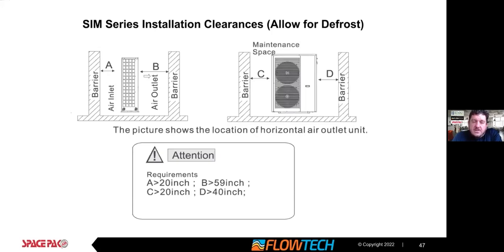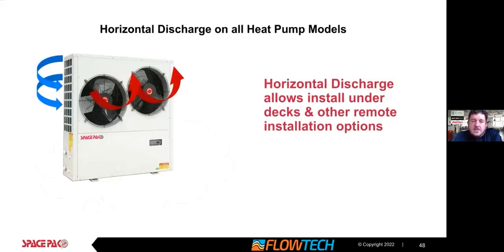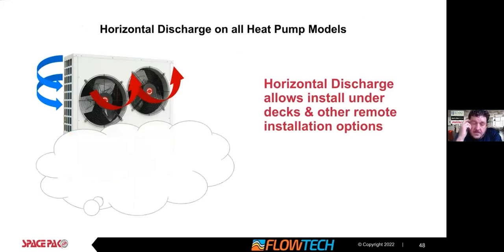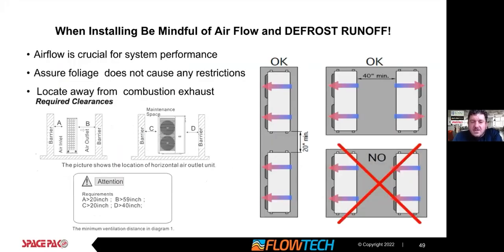This is the SIM unit, 40 off the right, 20 off the back, 20 off the left, and 60 off the front. This is an older model, a legacy product for SpacePak. This is pulling in the cold air off the back and hot air is coming off the front. You never get what you want. When you're commissioning a unit in the winter, it's blowing cold, and when you're commissioning a unit in the summer, it's blowing hot on you. So as a technician, it's one of those things.